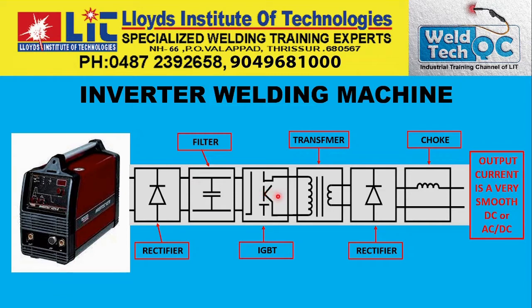And when it passes through the IGBT, it is converted back to alternating current with an elevated frequency as high as 20,000 Hz, as we discussed just now. This is again passed through a transformer here, to bring down the high voltage and low amps to low volts and high amps to suit welding.